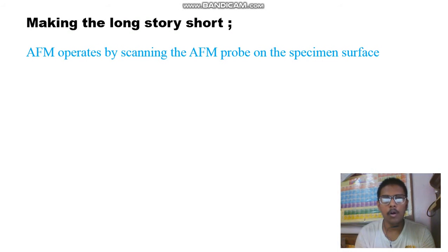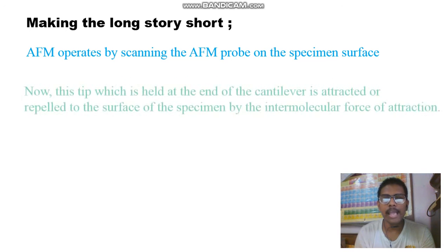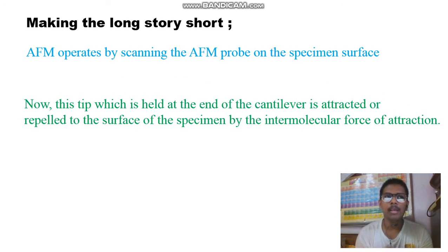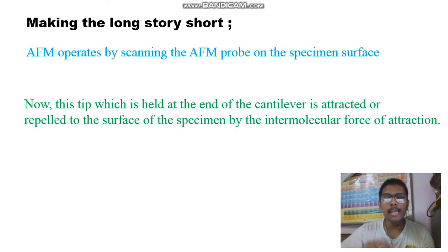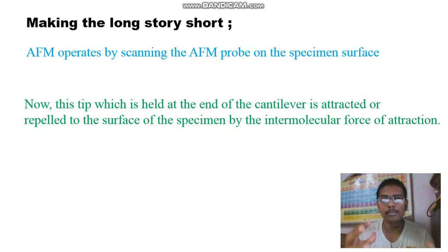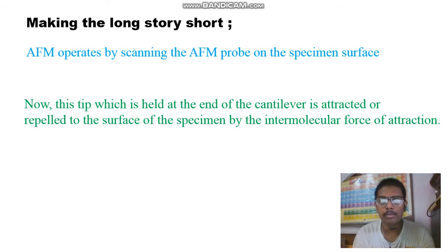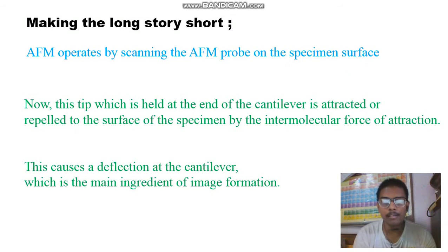The AFM principle is based upon three stages. AFM operates by scanning the AFM probe on the specimen surface, meaning the probe scans the whole surface. The tip held at the end of the cantilever is attracted or repelled to the surface by intermolecular forces. These variations in intermolecular force create variations in cantilever deflection, which is recorded by a laser at the photodiode, and thus the image is formed at your connected computer.